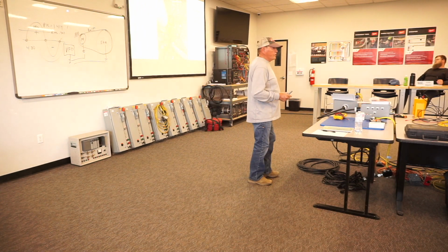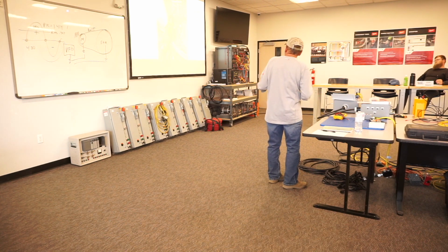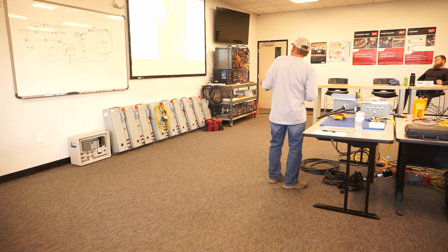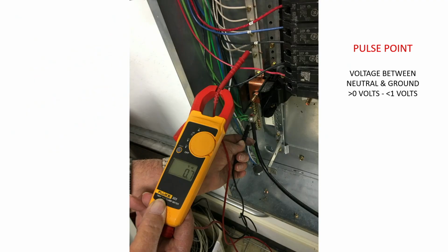This is a nice, easy test that you can conduct. I call it a pulse point. My goal here is to determine, between my neutral and my ground bus, if they are tied together somewhere in the building, I'm going to have voltage on my ground conductor. For instance, if the generator is neutral-ground bonded, and I've got a 3-pole ATS, I'm going to have voltage between the neutral and the ground. I don't want more than a volt. I want something greater than 0, because if it's 0, that means they're both tied together and there's no difference of potential. If I try to measure voltage across a piece of wire, I'm going to measure 0 because there's no difference of potential. So I measure 0 on that pulse point, which is in a panel.